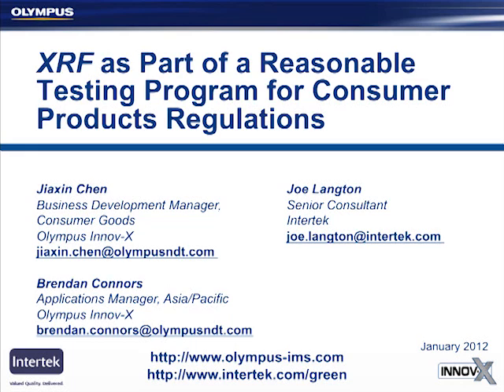One question came up on halogen-free applications. Can XRF be used for halogen-free applications? I didn't talk about that too much today. Halogen-free, if you're not familiar, is a voluntary standard that some manufacturers have signed on to limit the amount of chlorine and bromine that are going into plastics. XRF can be used to detect those two elements, and so the short answer is yes, you can use XRF for halogen-free applications. Chlorine's a lot more difficult to test for than bromine, though. Bromine, you can get a detection limit of a few ppm within a few seconds. For chlorine, you tend to need to run a bit longer tests.